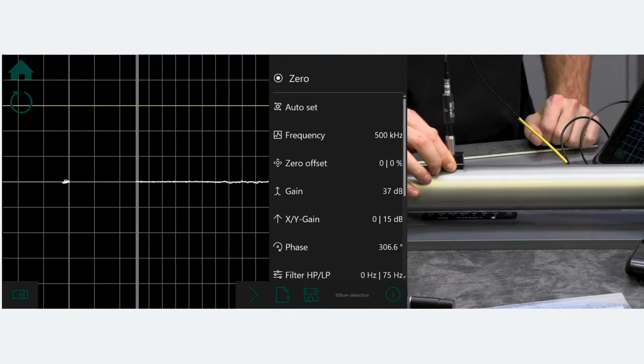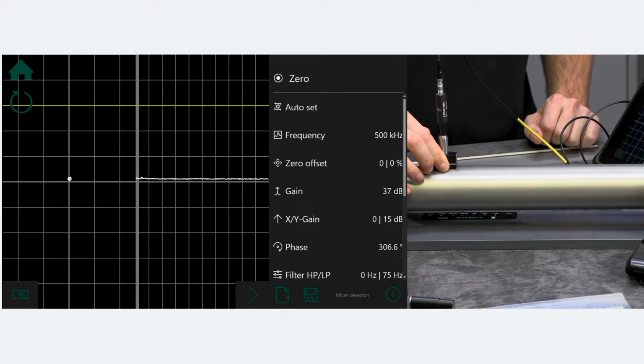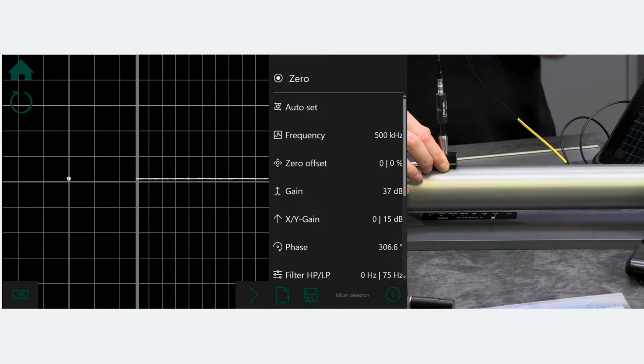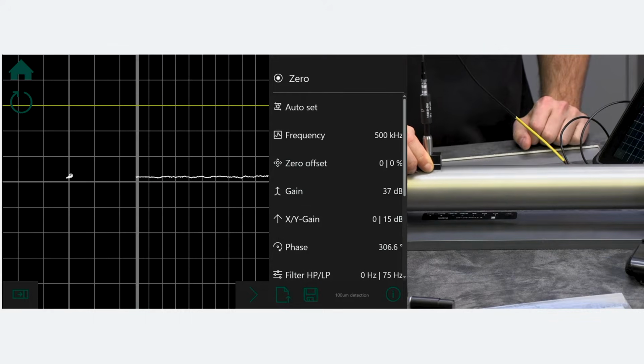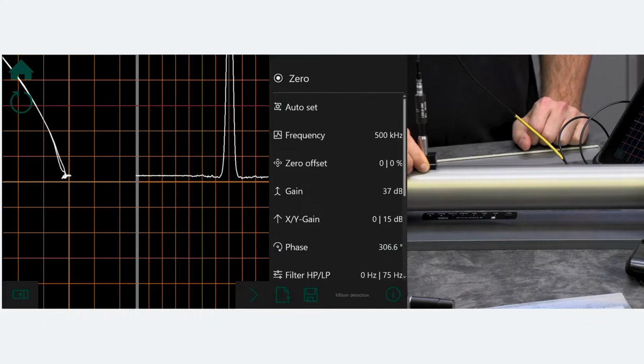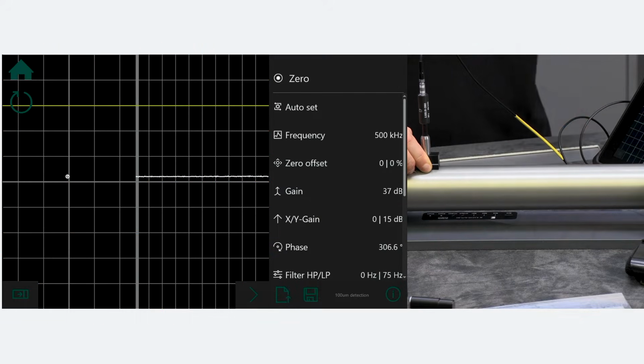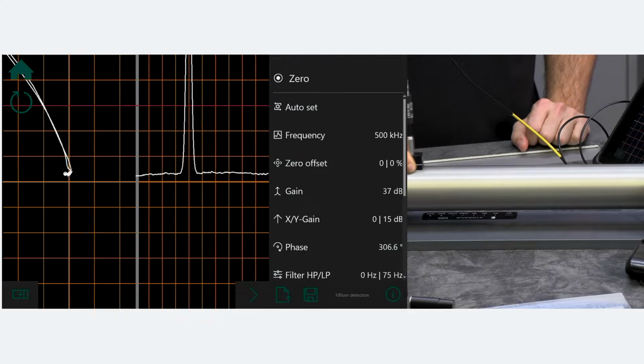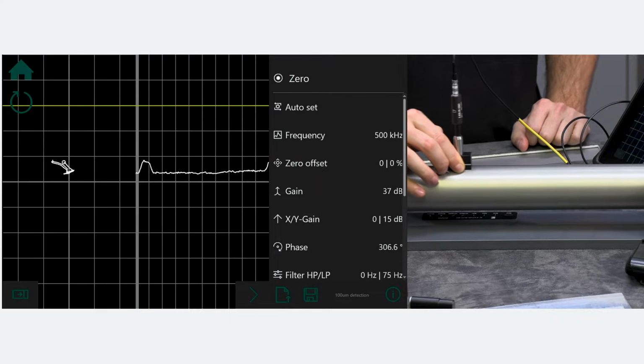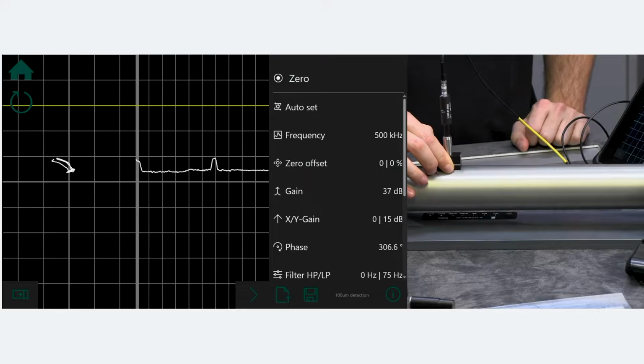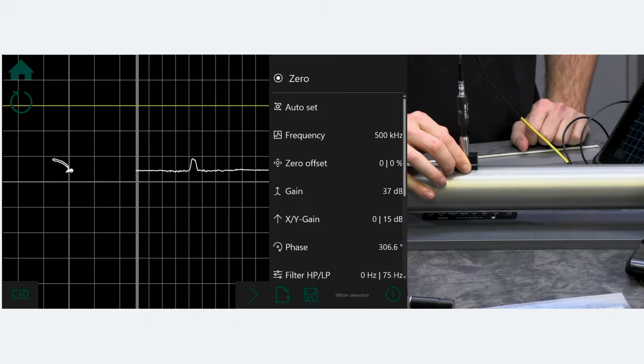Again, 0. Okay. And to get a feeling how big the signal is, if we scan over a crack which is 0.5 millimeter deep, it really comes out of the scale. So it's really a very small crack indication we can show here with the instrument.